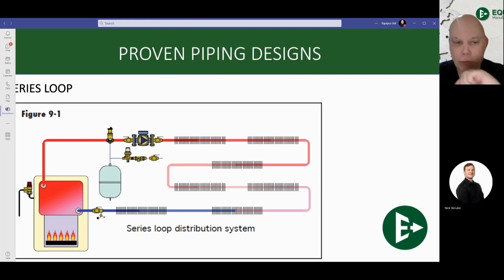We come out of the boiler, and the very first thing that you see on that red line is our high efficiency air separator. Right after that is our distribution pump. Attached to our high efficiency air separator is our expansion tank. This means that we are pumping away from the expansion tank. You always want to pump away from your expansion tank and not into your expansion tank, because if you pump into your expansion tank, it will absorb all the pressure that your circulator has created, usually resulting in a low flow situation or even a negative pressure situation. This is more of an advanced technique, which we'll get into in a later training, but just know for your basic understanding, always pump away from your expansion tank.